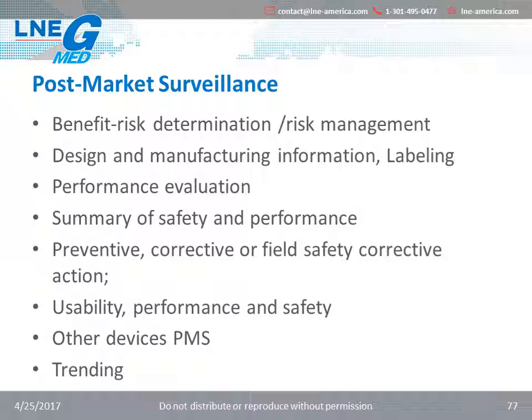performance referred to in Article 29, for the identification of needs for preventive, corrective, or field safety corrective actions, for the identification of options to improve the usability, performance, and safety of the devices, when relevant, to contribute to the post-market surveillance of other devices, and also to detect and report trends in accordance with Article 83.